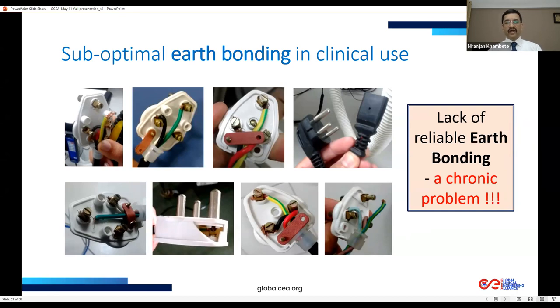Lack of reliable earth bonding is a real chronic problem. Even if you do electrical safety testing once in 6 months or once in 12 months, in between there could be a situation where the earth bonding got compromised due to low quality 3-pin plugs. In low resource settings, perhaps we can't afford very high quality devices to ensure the earth bonding is equally good. Can I have the next slide, please?